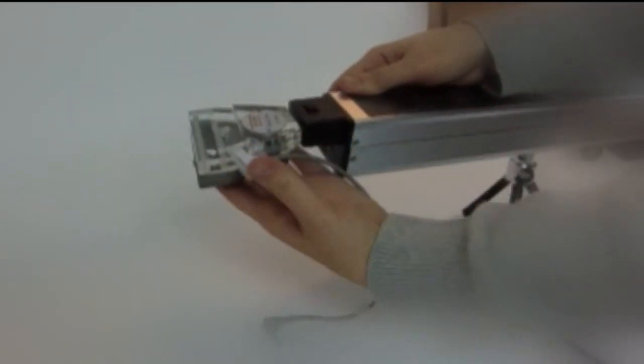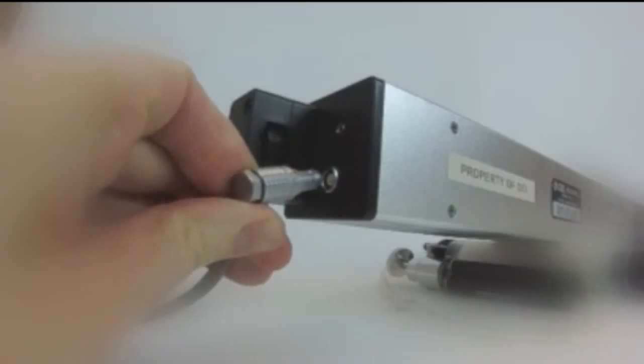Here we are using the LC3 leaf chamber as an example. Check that the air and leaf temperature sensor fits securely in place without bending any wires. The PAR sensor will slide into place within a slot located on the side of the chamber. Connect the air and leaf temperature sensor and PAR sensor plugs into their respective locations on the head end of the CI-340. Don't forget that the air and leaf temperature sensor are delicate and require a strong locking connection port. Take care when connecting and disconnecting the air and leaf temperature sensor to line up the red dots.